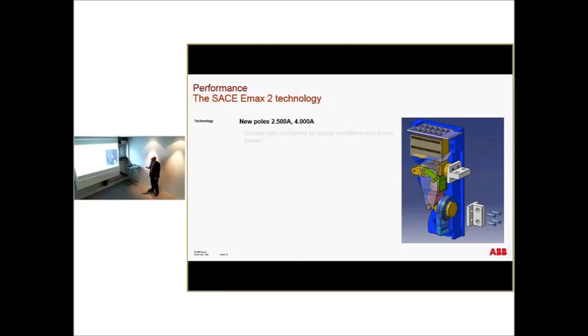Here, basically what we've done, we decreased the height. So this one is much smaller now because we tend to get the movement of the mechanism in a more horizontal way. So we reduced by 30% the heat loss inside the breaker. We have a circular pole, which means that you put the Rogowski coil here. The square one that everybody else has gives an accuracy that is not better than 2.83%. This one gives an accuracy of 2%.